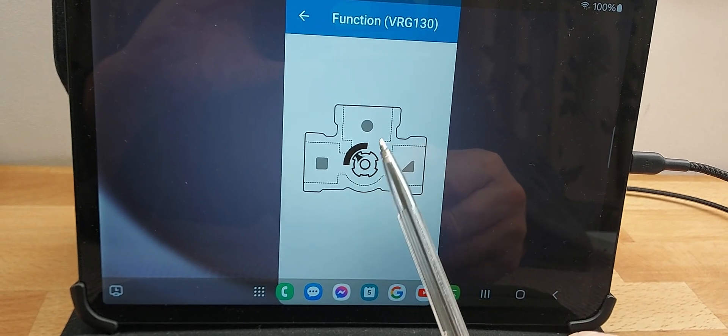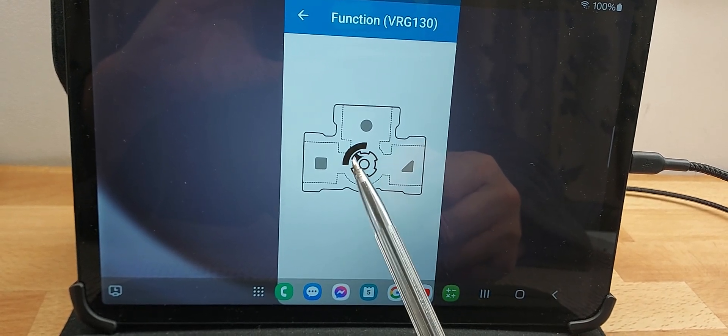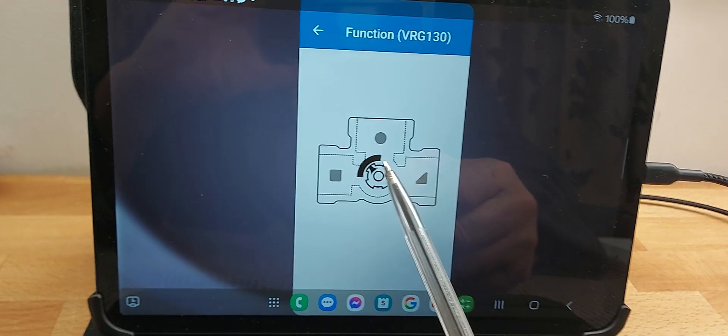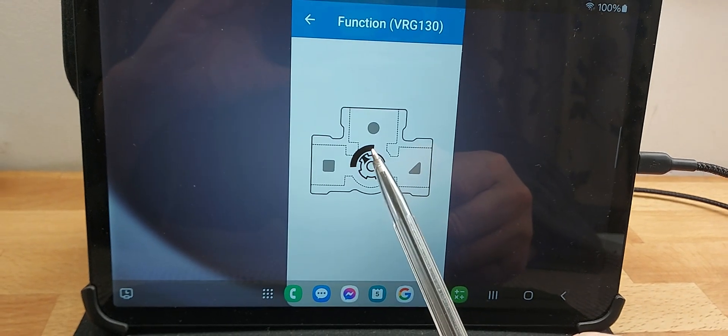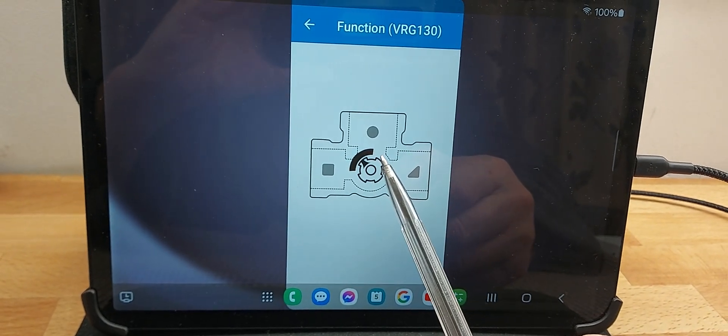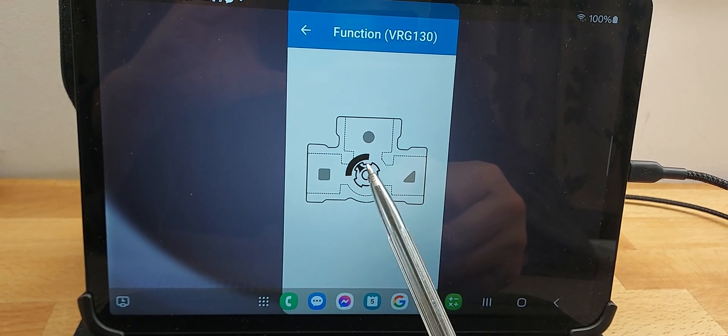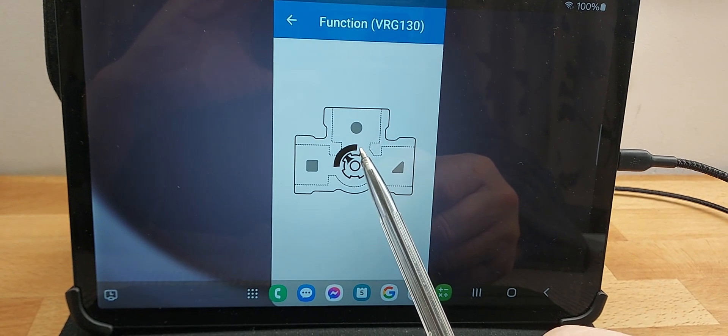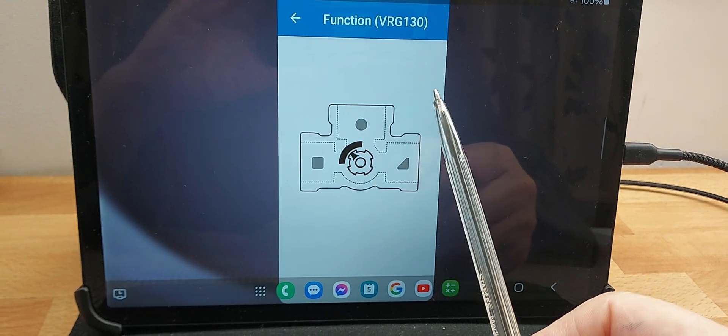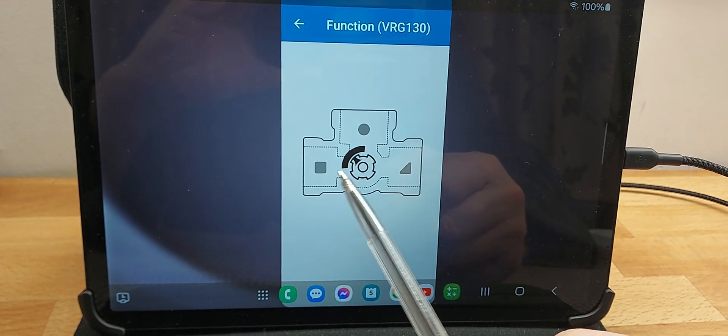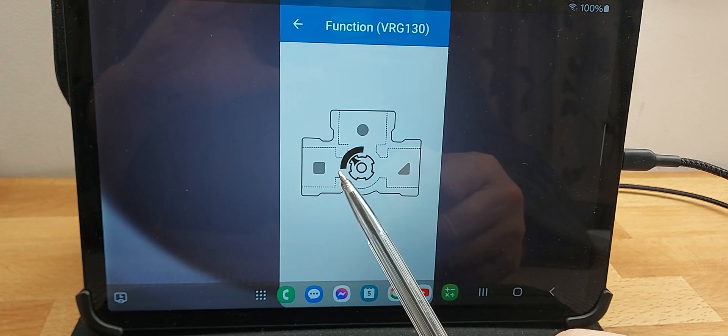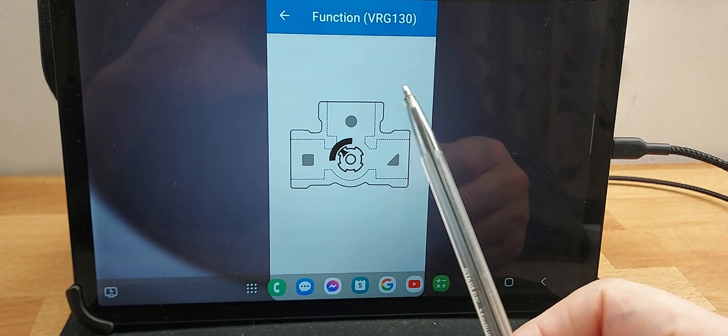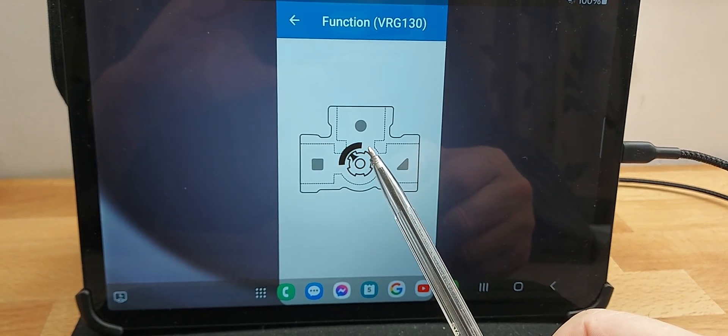As you can see in the middle position, it's going to allow blended water coming through from these two circuits. This is the aperture here. This is what affects the authority. If you imagine that gap was two inches diameter and you had a trickle of water coming through, there's going to be no authority.